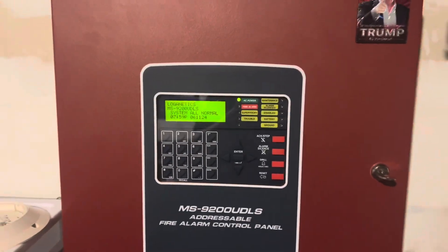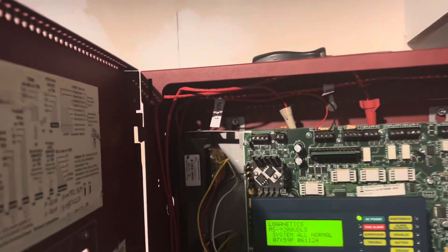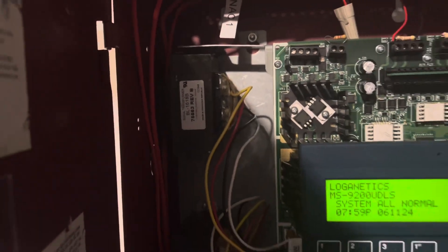All right everyone, you can see that we have a new fire panel. We have a Fire-Lite MS-9200UDLS. We got the batteries, all of our wiring, and we do have some FPLP, so I'm not using that crappy stranded stuff anymore. Dual transformers — it actually came with the second one, I didn't buy it.